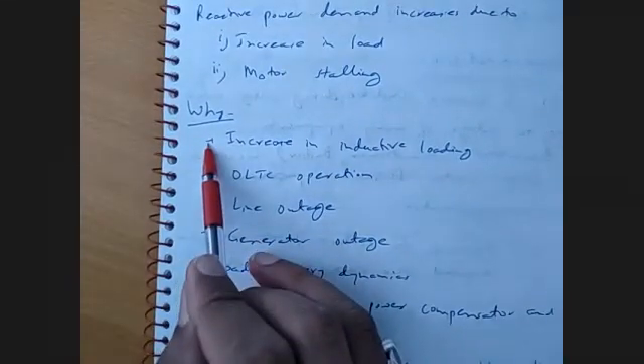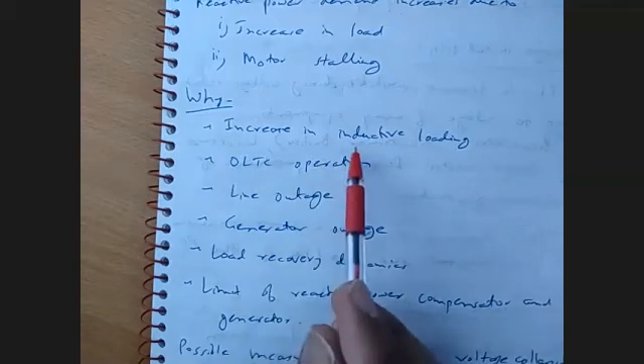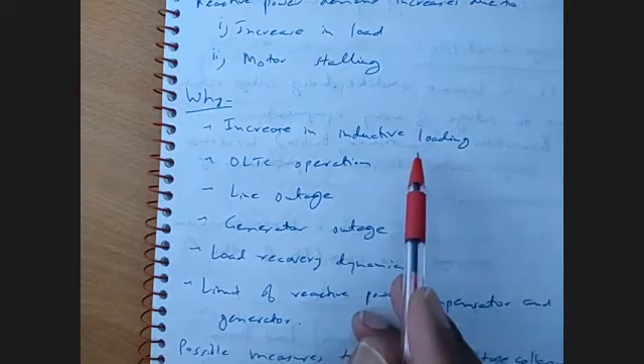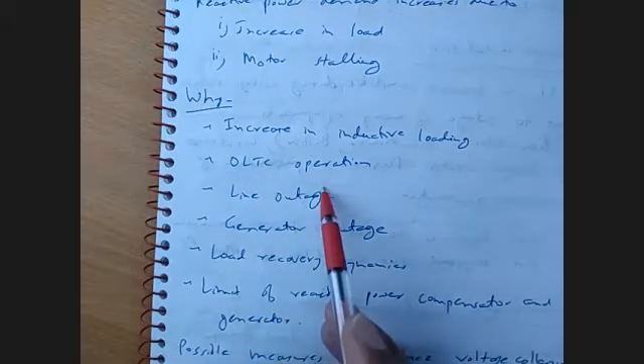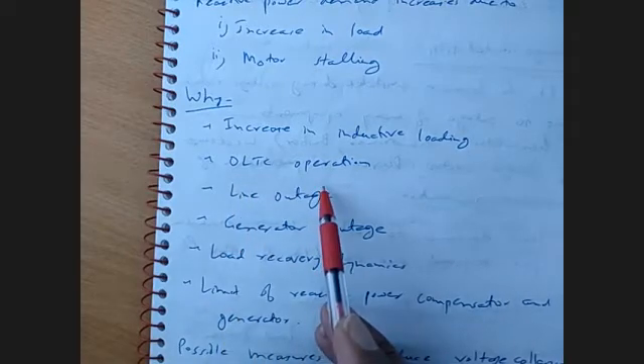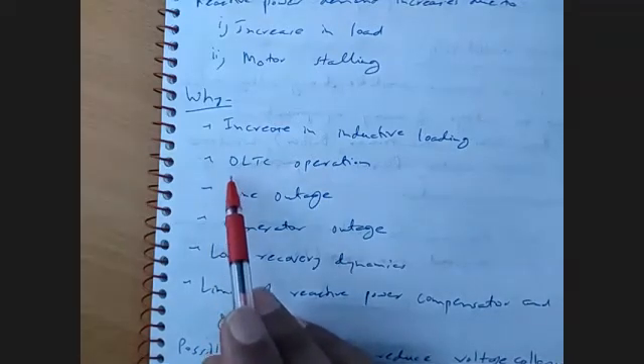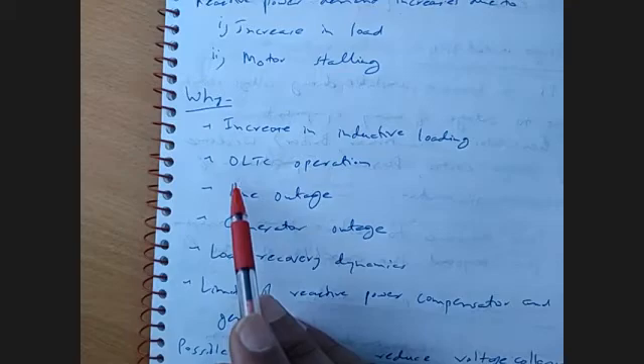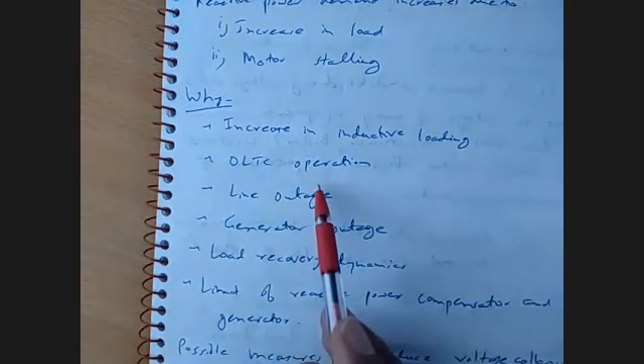Now, why does voltage collapse happen in a power system? Voltage collapse happens due to various aspects. Some of the issues we have chalked out: voltage collapse can happen due to the increase in the inductive load of the system, which will increase the reactive power demand of the system, and due to the increase in the reactive power, the system is not able to recover. Then the second major concern is the on-load tap changer operation, that is OLTC operation. As we have discussed in the previous class, a major issue of voltage collapse is due to the on-load tap changer of the transformers.